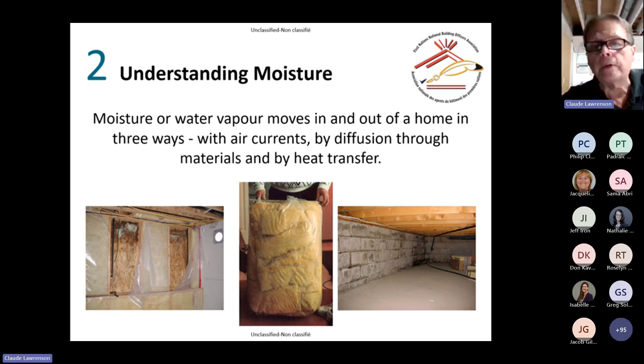Moisture tends to move from an area of higher to lower temperature and moisture content, thus often referred to as infiltration coming in and exfiltration going out. These photos provide obvious signs of moisture movement. The laws of physics govern how moist air reacts with various temperature conditions. The temperature and moisture concentration at which water vapor begins to condense is called dew point. We'll talk a little bit more about dew point shortly.